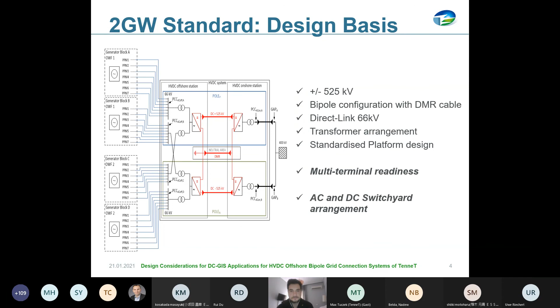Okay, that's strange. Nevertheless, what we mean by multi-terminal readiness is that the system should not prevent the future extension to a multi-terminal system. Below, the picture for some reason isn't illustrated correctly, but it shows the possibility to connect our point-to-point HVDC systems to another offshore terminal and then to the grid of the UK. In that sense, it would be a 4-terminal system, and in the second topology our offshore platform would connect directly to the UK side for a 3-terminal application. In both scenarios, the DC yard of the platform station would have to have one additional departure line towards the UK.